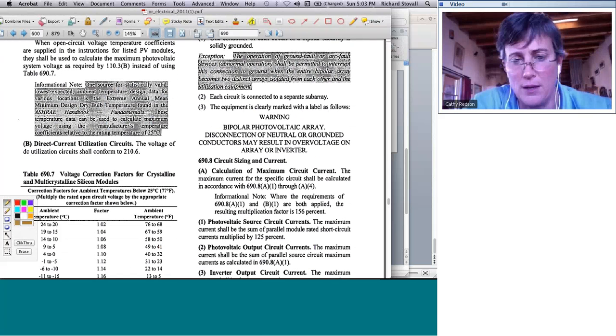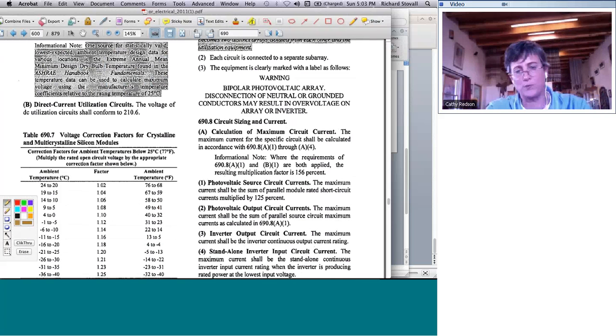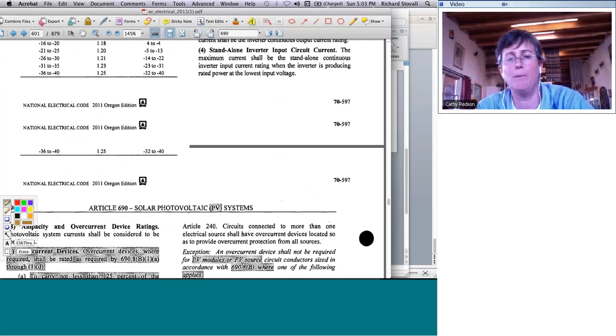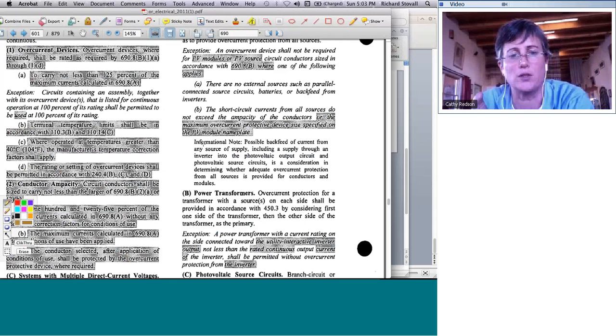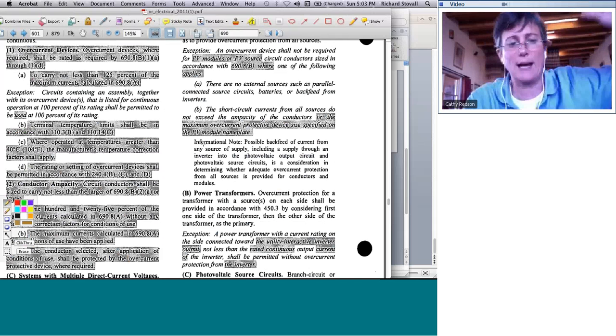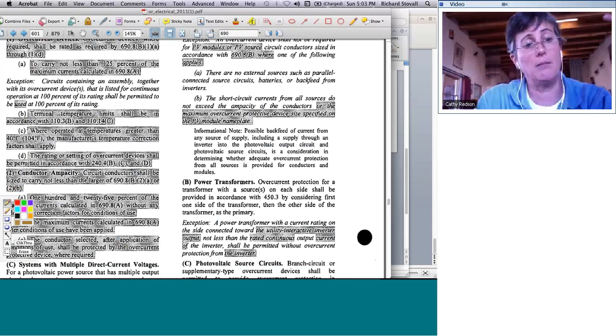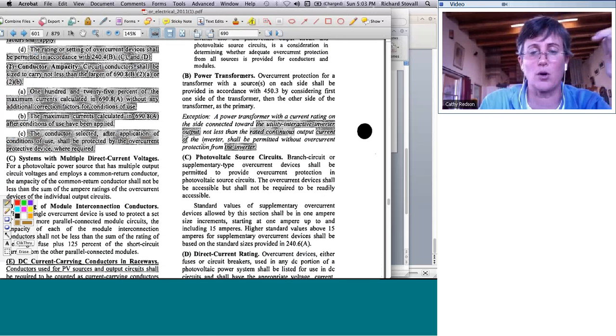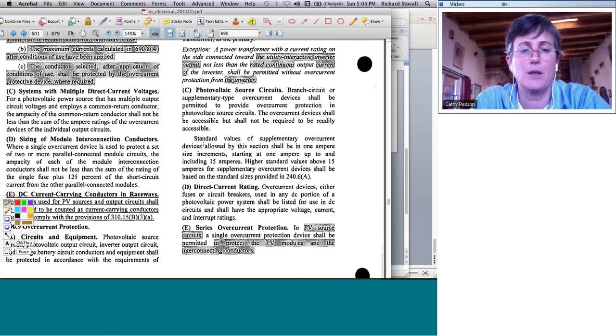And by separating out the two, you won't ever put the wrong multiplier in the wrong place. Okay, so that's max current. And on the labeling, they're looking for instantaneous numbers, where they're requiring you to indicate four things. What's the rated current on this system? What's the rated voltage? That's from the minute you power it on, no irradiance. Boom, what's it rated at according to the label on the system? But then when they say max current and max system voltage, that's where they want the temperature corrected or potentially the irradiance affected numbers listed there. Okay.